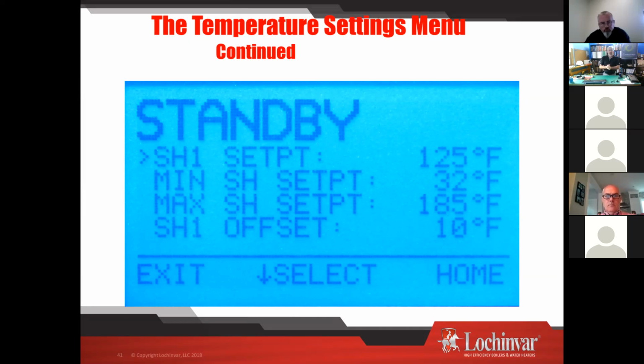I could use that for a couple of different things. One is maybe I'm operating within a heat pump loop, and I want to set a maximum never to exceed type of temperature. I'd go into my max space heating set point and say, hey, I don't ever want to exceed 140 degrees or 130, whatever it is. Minimum at 32. A lot of times I look at this, this is your homeowner protection right here.